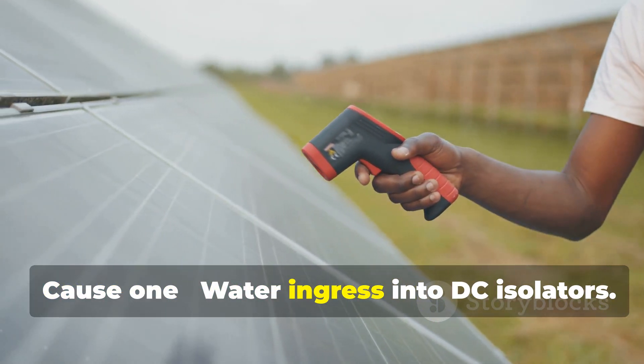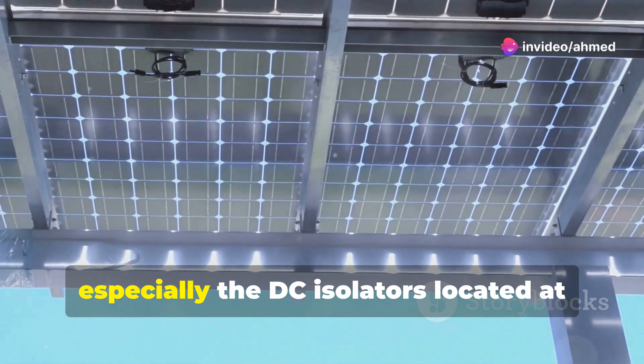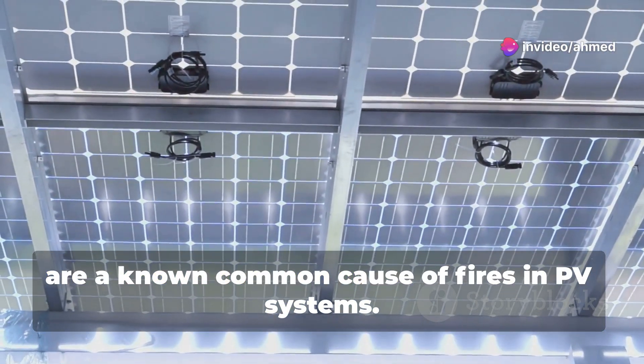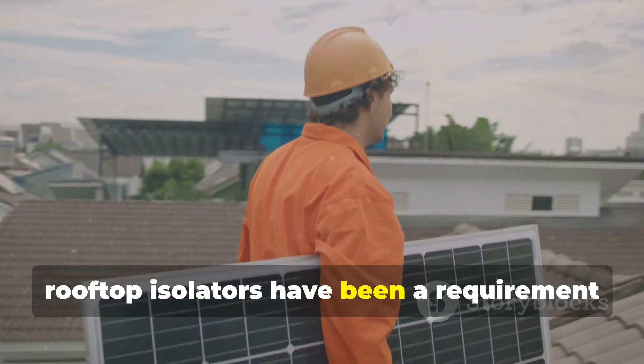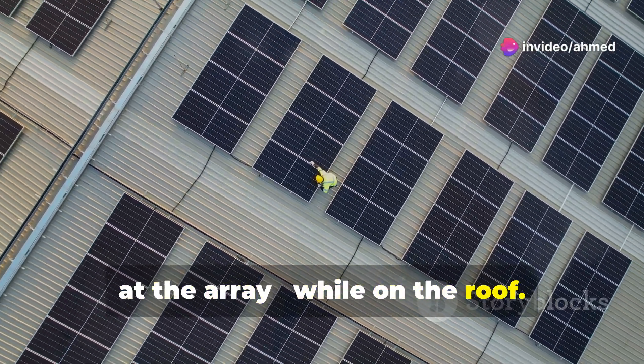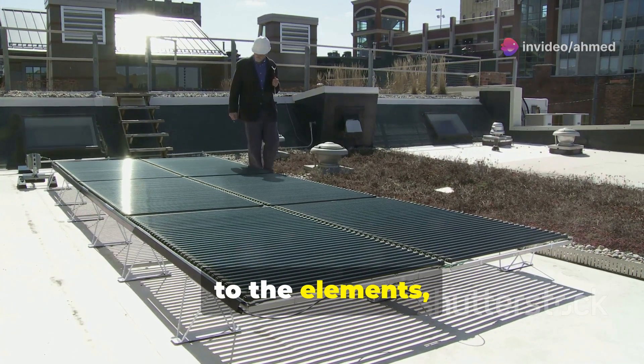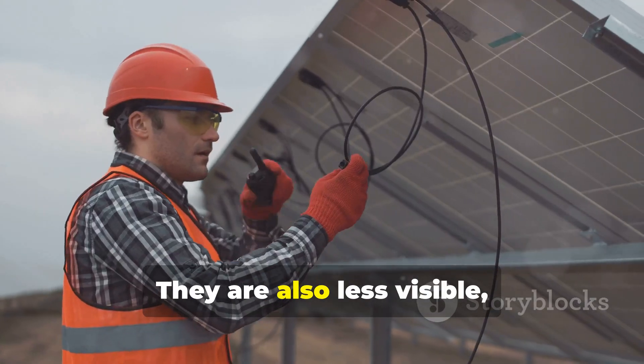Cause 1: Water Ingress into DC Isolators. DC isolators, especially those located at the roof, are a known common cause of fires in PV systems. Historically, rooftop isolators have been a requirement in Australia to allow fire safety services and other workers to disconnect the system at the array while on the roof. However, with rooftop isolators being more exposed to the elements, they are more prone to damage and deterioration.